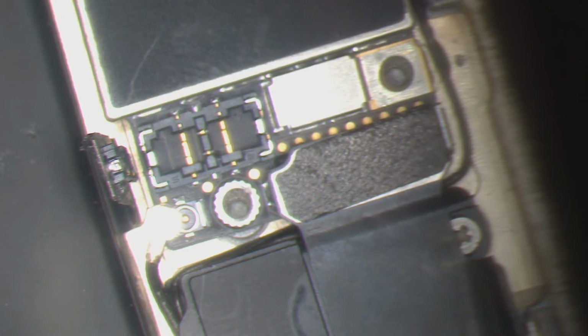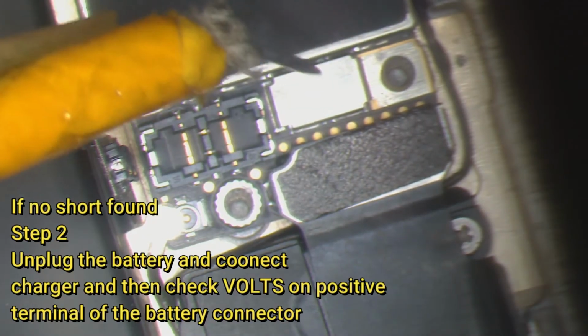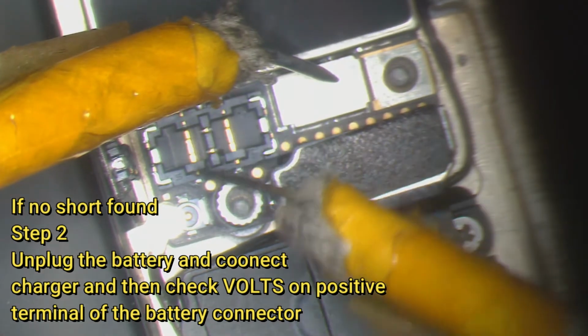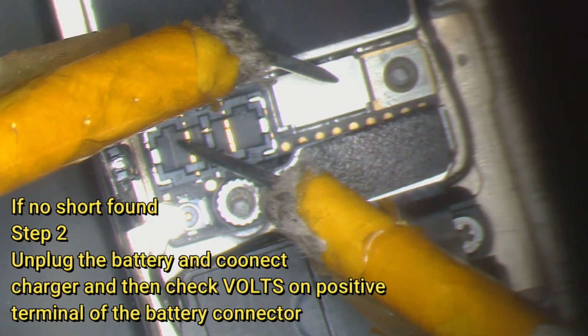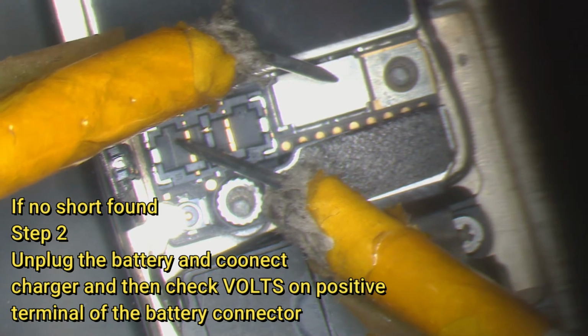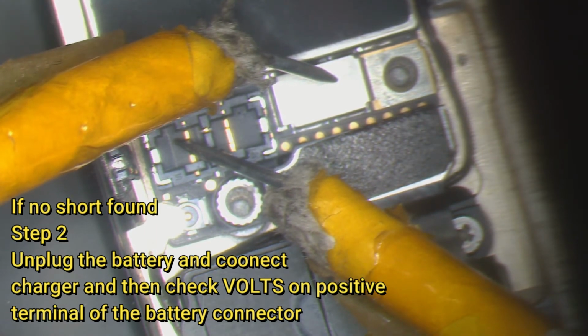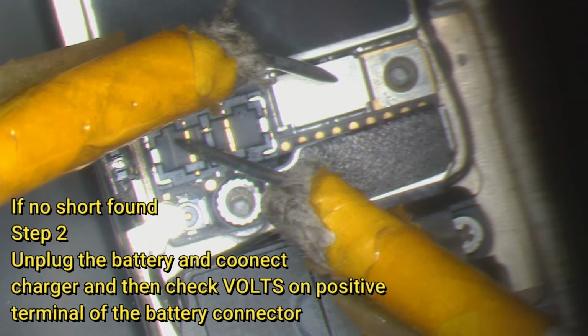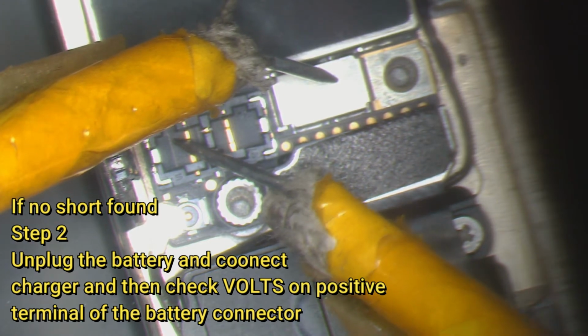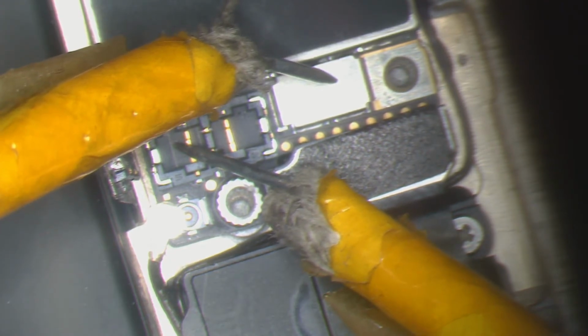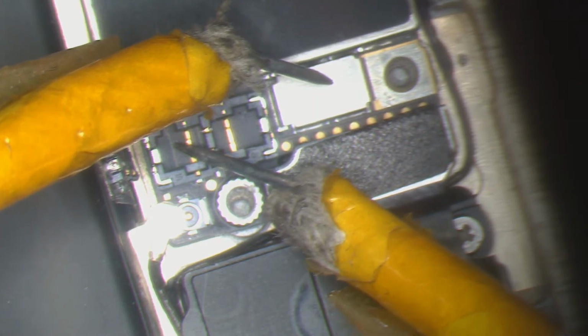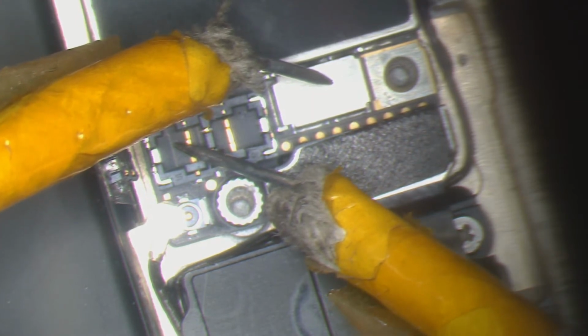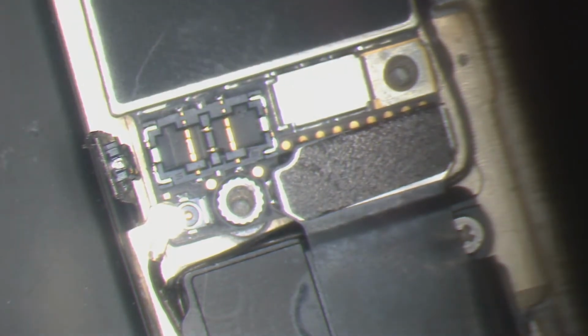Put the meter on 20 DC. Again, the black probe goes to the ground and the red probe goes to the positive side of the battery terminal. It shows here 0.53 volts. So that is a simple basic check that the TriStar is not working. If the TriStar were working, it should have shown 3.75 volts on the battery terminal without the battery connected when you plug the charger in.